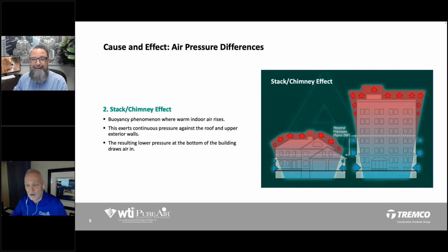Exactly, Troy, and it all depends on the height of the building as well. How many stories is the building? The taller the building, the greater the stack pressures. The greater the temperature difference from inside to the outside, the greater the stack pressures. Now, in the north, in the winter you get the cold. As we're showing here, cold air gets in, gets warm, buoyant, and travels up through the top. The neutral pressure plane is usually sitting around, or floats back and forth around, the center of the building, and that's where the infiltrating air changes to exfiltrating air.